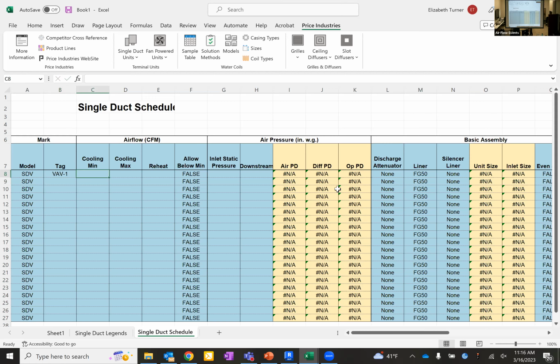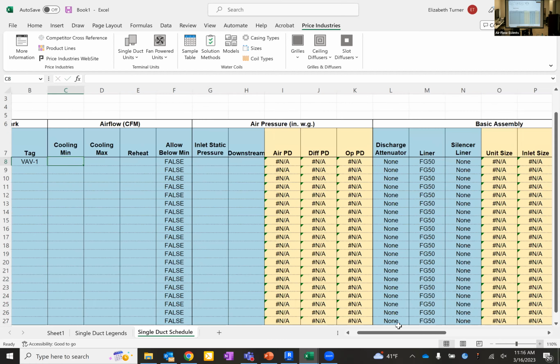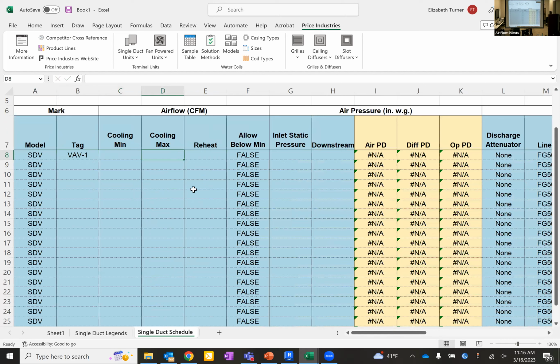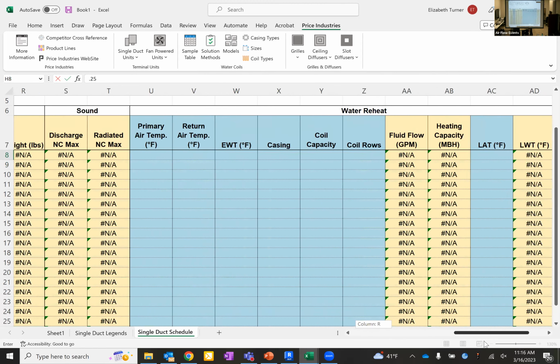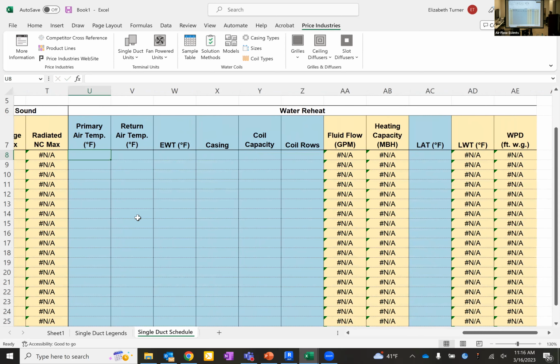So we'll select a sample here, zoom in a little bit more. Let's say my max is 800 and we always design for 20% minimum. So I'm 0.2 times my max, still Excel. I can use my normal functions here. Maybe reheat is 50%, 0.5 times fully max. Inlet static pressure, usually about 1 inch. Downstream, we'll say 0.25. I'm gonna scroll all the way over to my water coil section here. Primary air temp, usually 55, 75 return is pretty common.